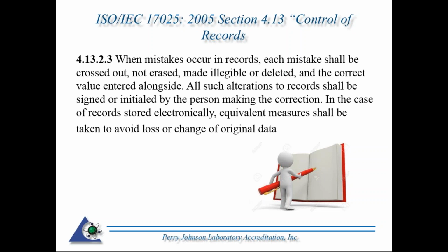I've actually seen it done while witnessing a calibration where a mistake was made. I saw the individual just scribble through and write the correct answer, and right away pointed to this area of the standard, went back and looked, and I've seen it as a reoccurring issue. So it's just something you need to be made aware of, that you are creating a record. And again, these actions need to be taken for handwritten records.